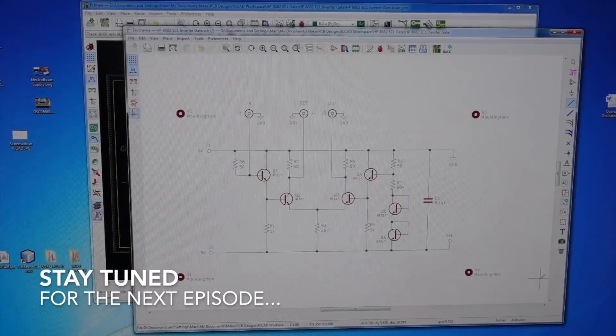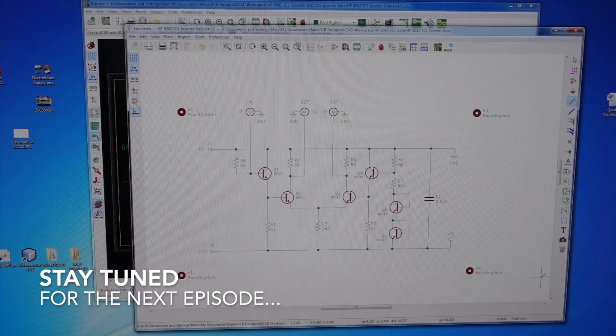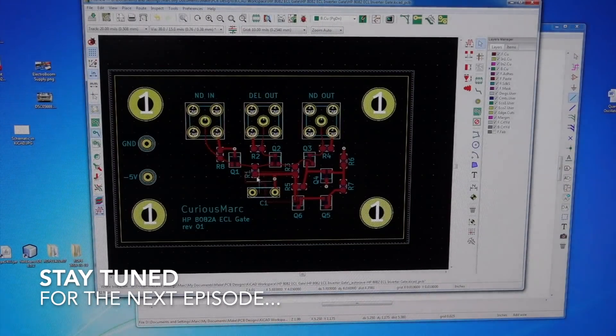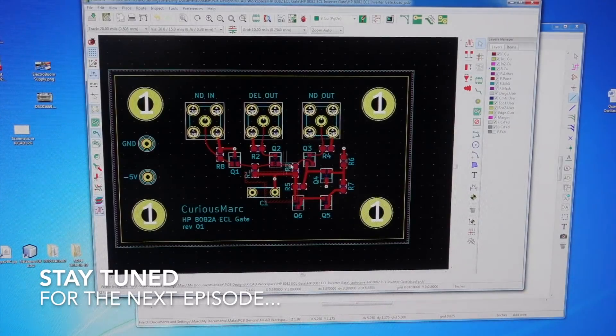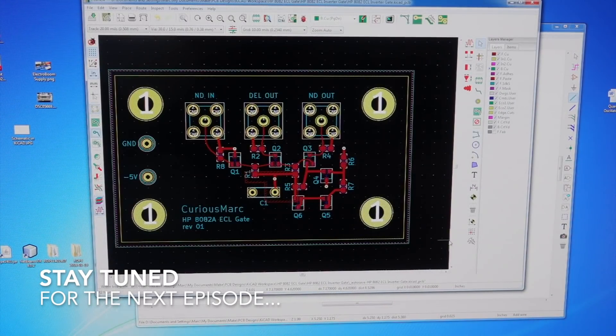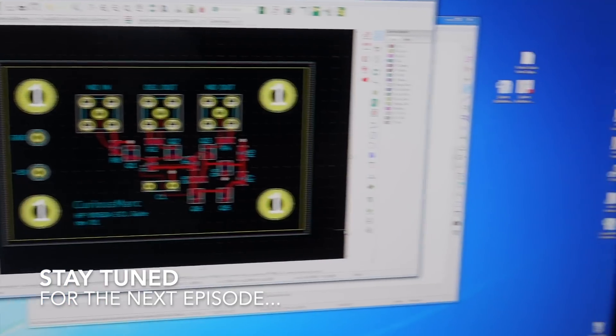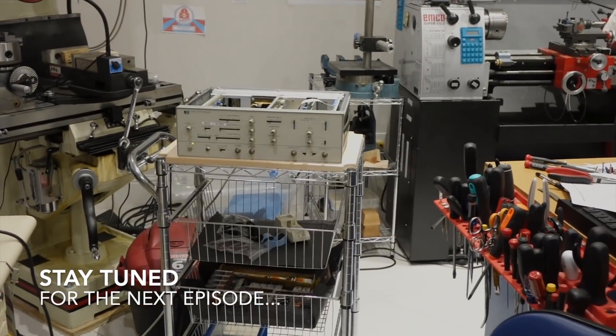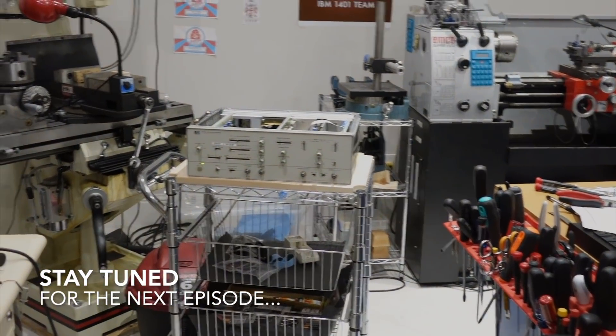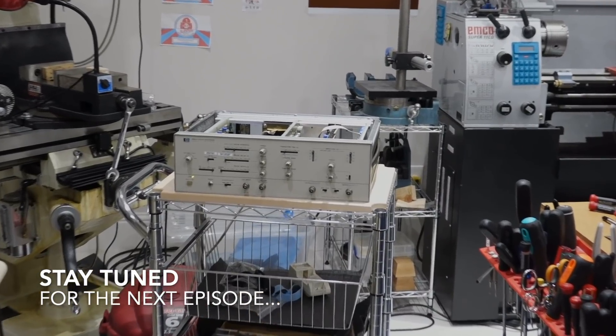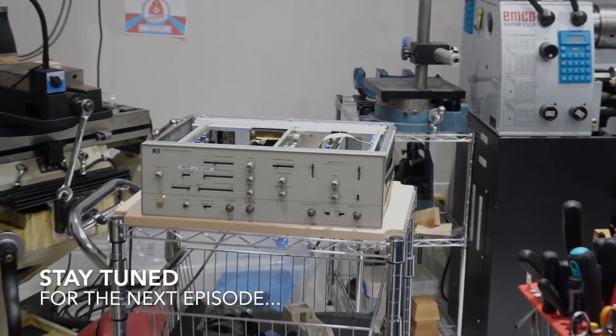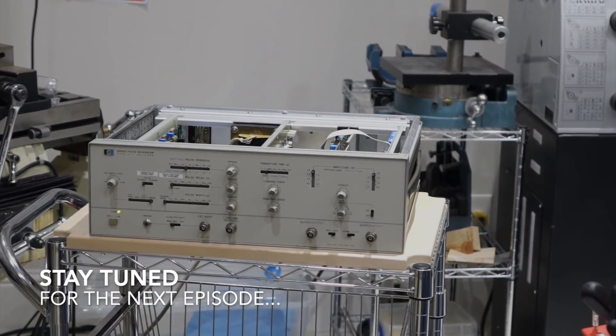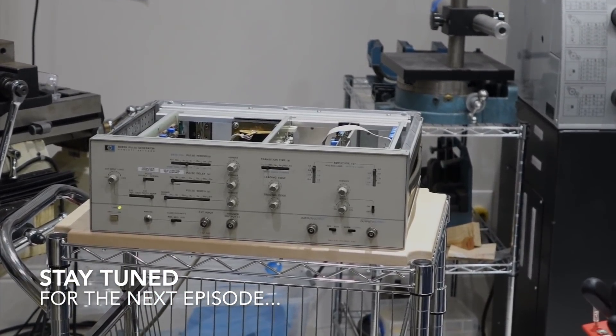So I already made the circuit, and I made a little board out of it with surface mount transistors. For now, we'll consider our HP 8082 repaired. And when the board comes back, we'll have some fun and see if we can repair it a hundred percent.